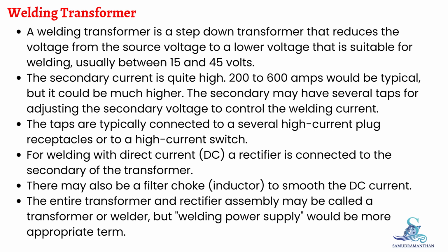Welding transformer. A welding transformer is a step-down transformer that reduces the voltage from the source voltage to a lower voltage that is suitable for welding, usually between 15 and 45 volts. The secondary current is quite high. 200 to 600 amps would be typical, but it could be much higher. The secondary may have several taps for adjusting the secondary voltage to control the welding current. The taps are typically connected to several high-current plug receptacles or to a high-current switch.